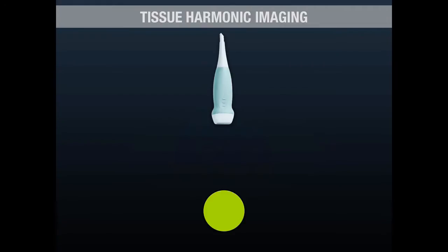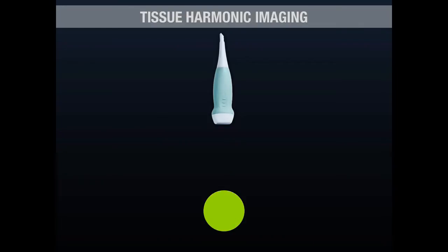And in most cases, that's the fundamental frequency that you're used to discussing when you discuss the frequency range of an ultrasound transducer. So, for example, this is a phased array transducer. It'll typically have a frequency somewhere in the range of 1 to 5 megahertz, or a million hertz. And that is the fundamental frequency. Let's say that it's operating at 2 megahertz for the sake of argument.